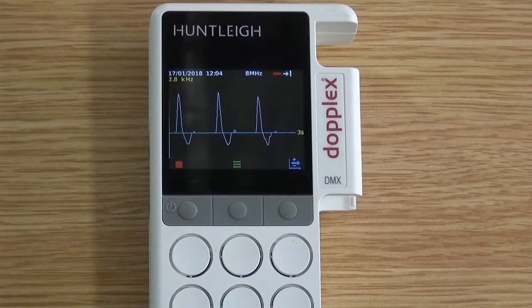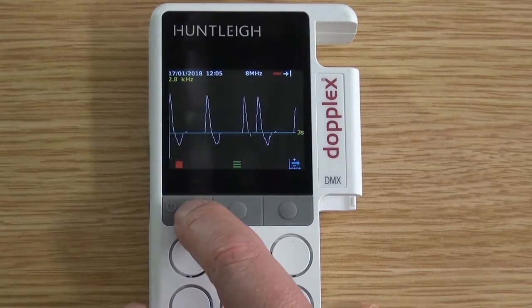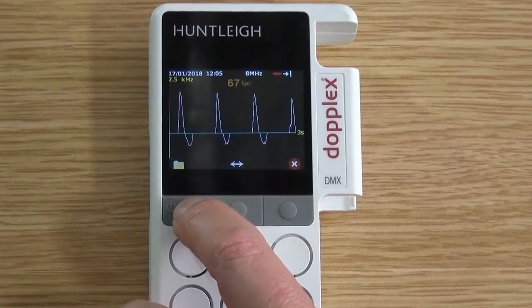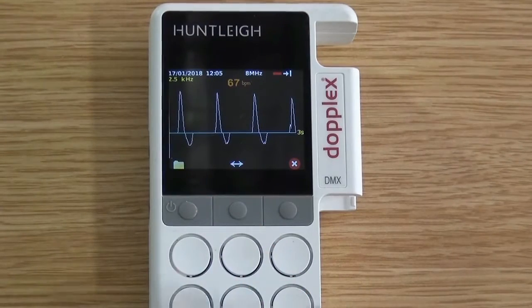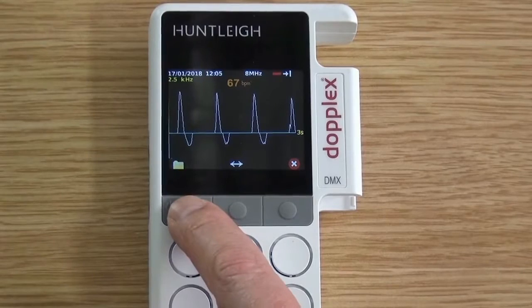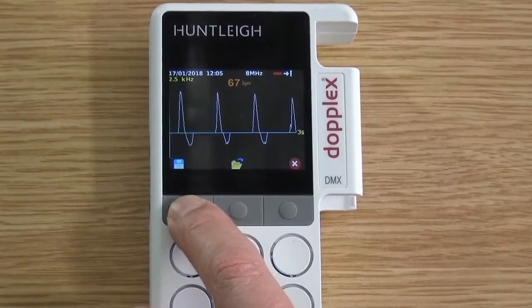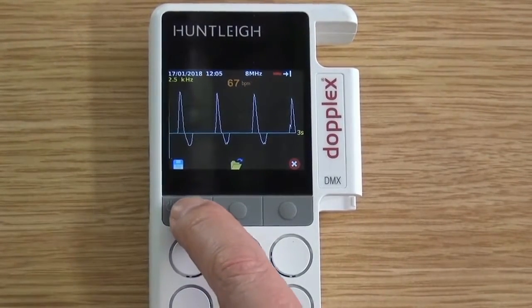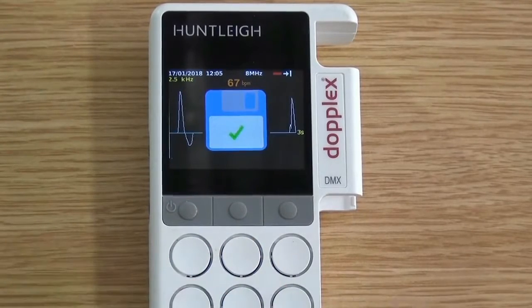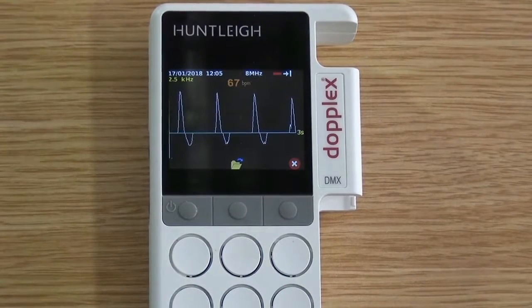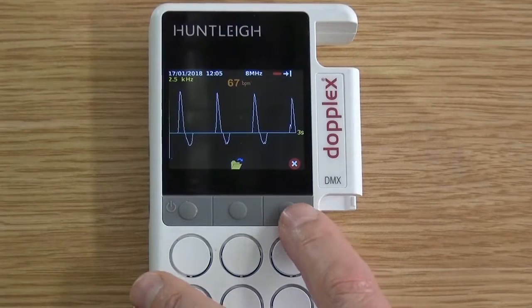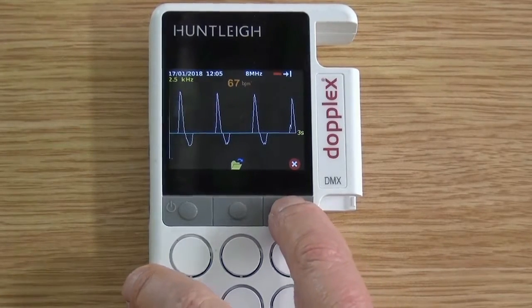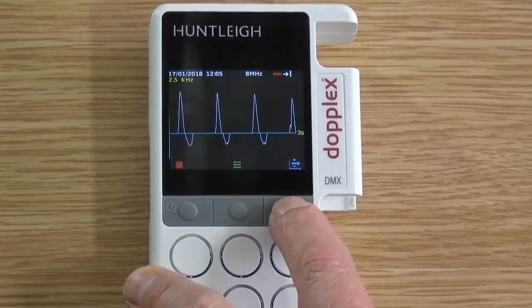Once a waveform has been found, press the stop button. If you are happy with this waveform, press the left button twice as shown; this saves the waveform to the memory card. To run real-time again, press the red cross twice.